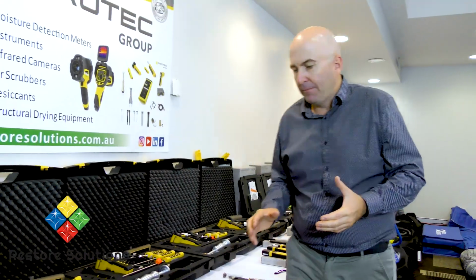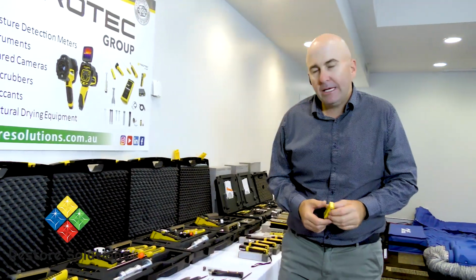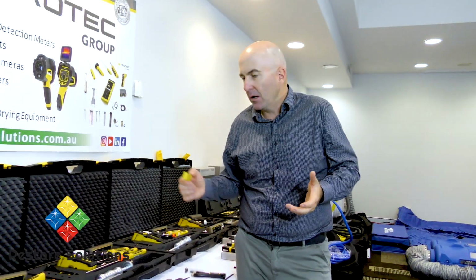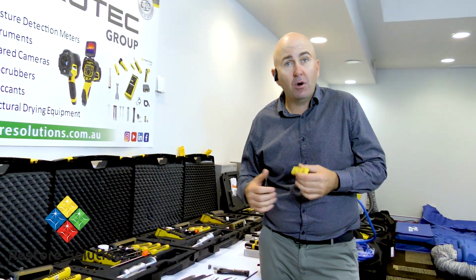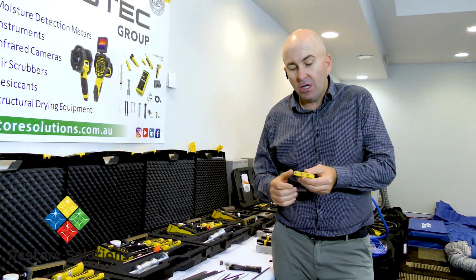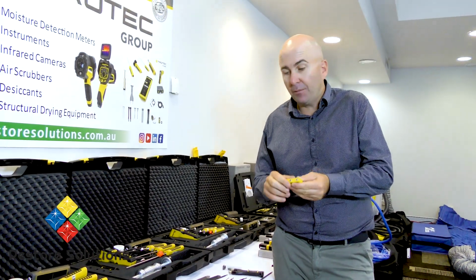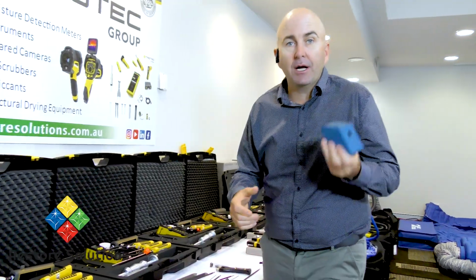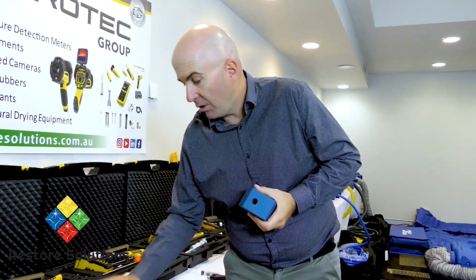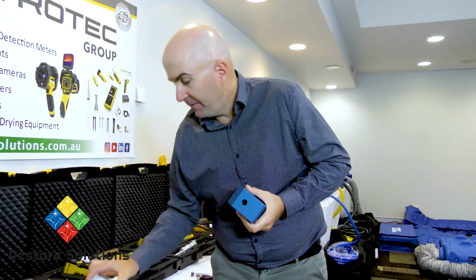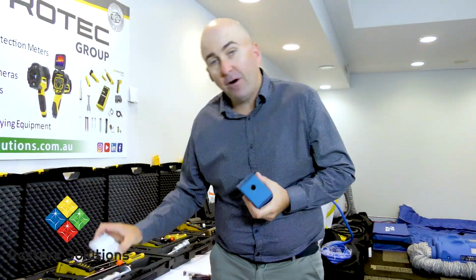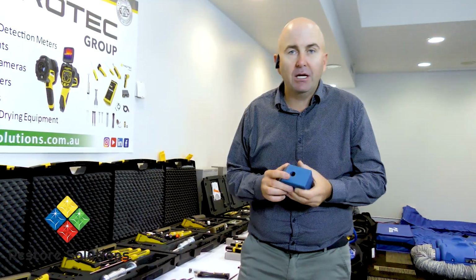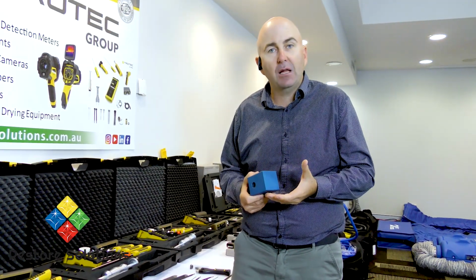So the beauty about all our meters too is we can actually calibrate them on the meter. You've got plus or minus you can do on the meter. So you can go through and check all the pin meter with this calibration block. And then for your hygrometer, you've got your little ampoules here, which are either 80% relative humidity, 50% relative humidity, or 35% relative humidity. You put your ampoule in and you put your hygrometer in to see if it's calibrated. So you can check your own calibration on your own meter, and then adjust your meter accordingly, instead of sending it away for expensive calibration.